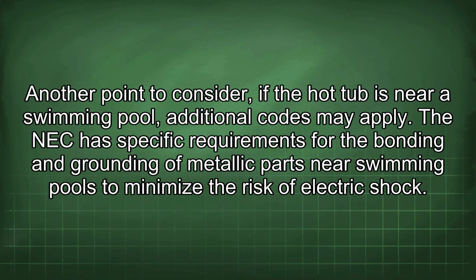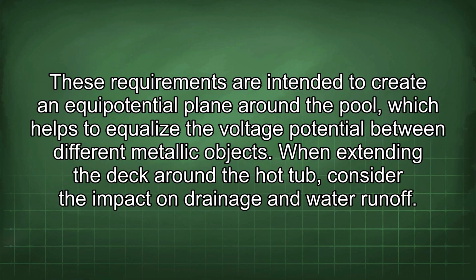Another point to consider: if the hot tub is near a swimming pool, additional codes may apply. The NEC has specific requirements for the bonding and grounding of metallic parts near swimming pools to minimize the risk of electric shock. These requirements are intended to create an equipotential plane around the pool, which helps to equalize the voltage potential between different metallic objects.